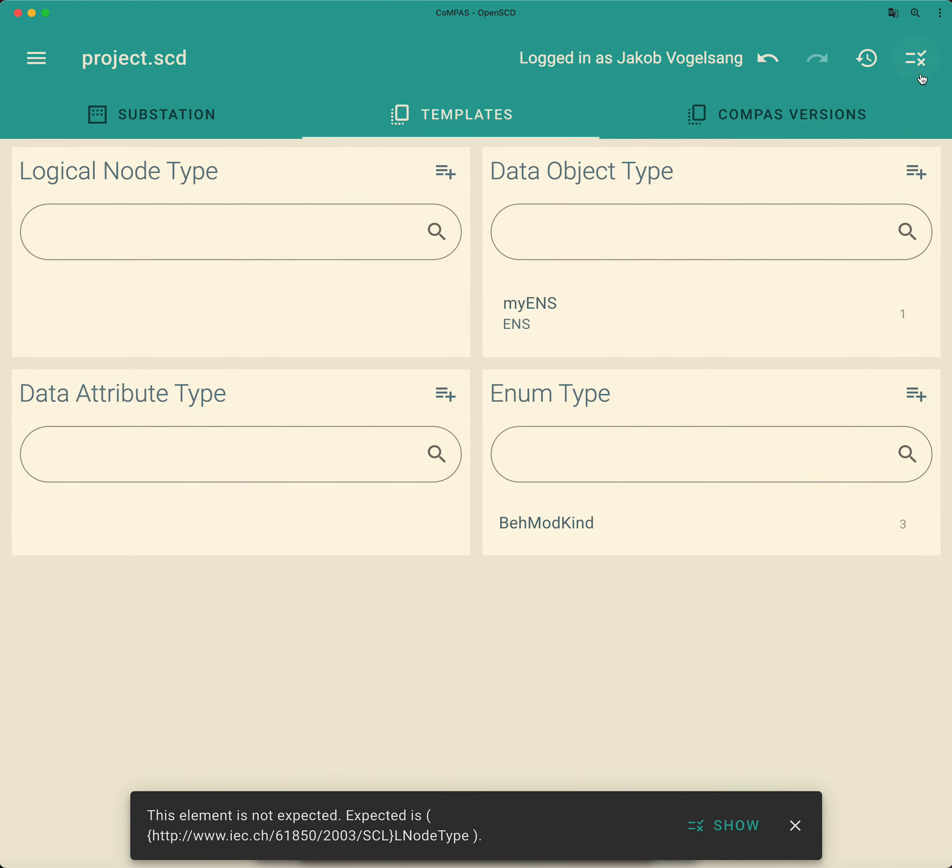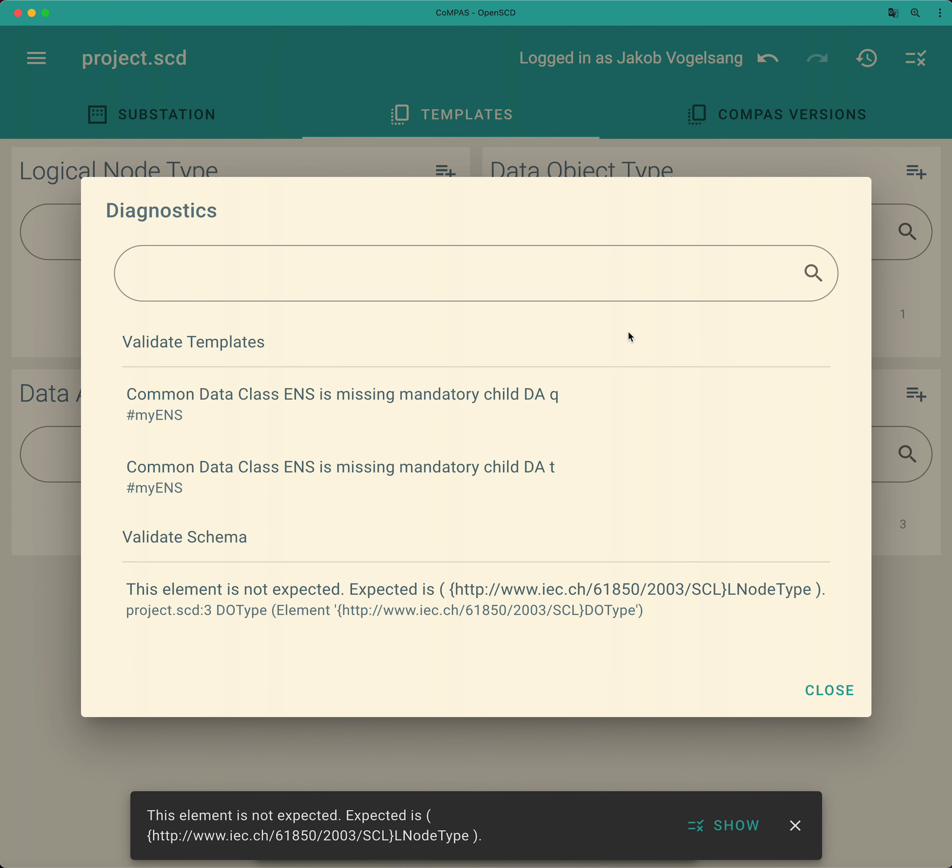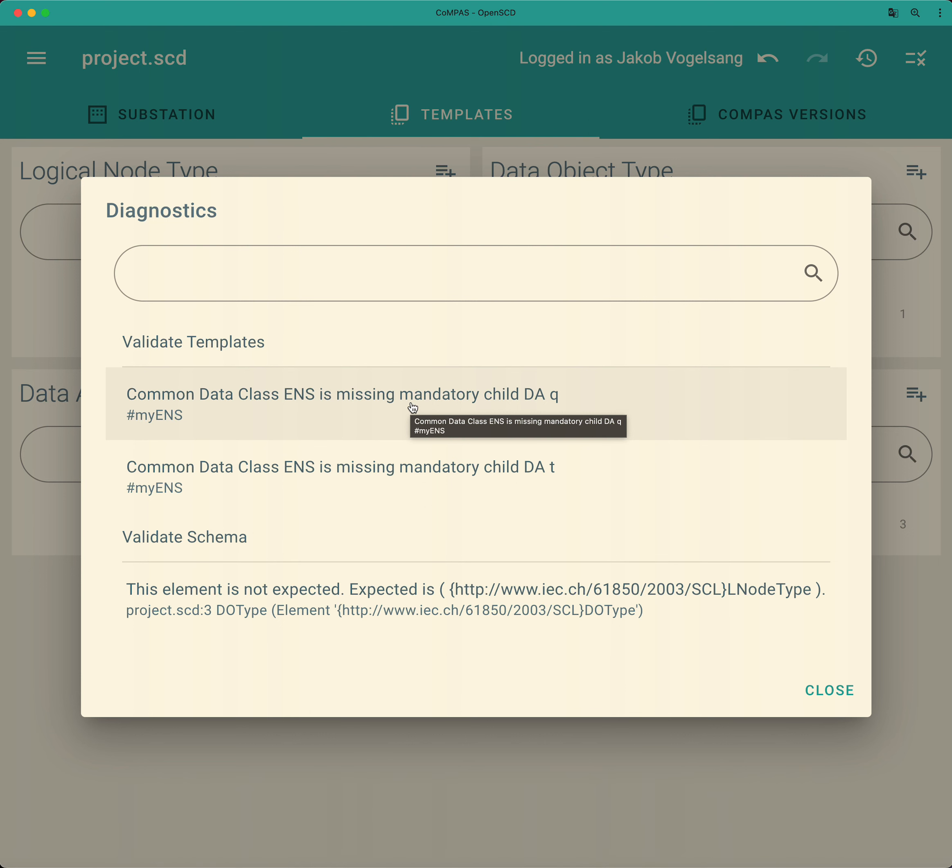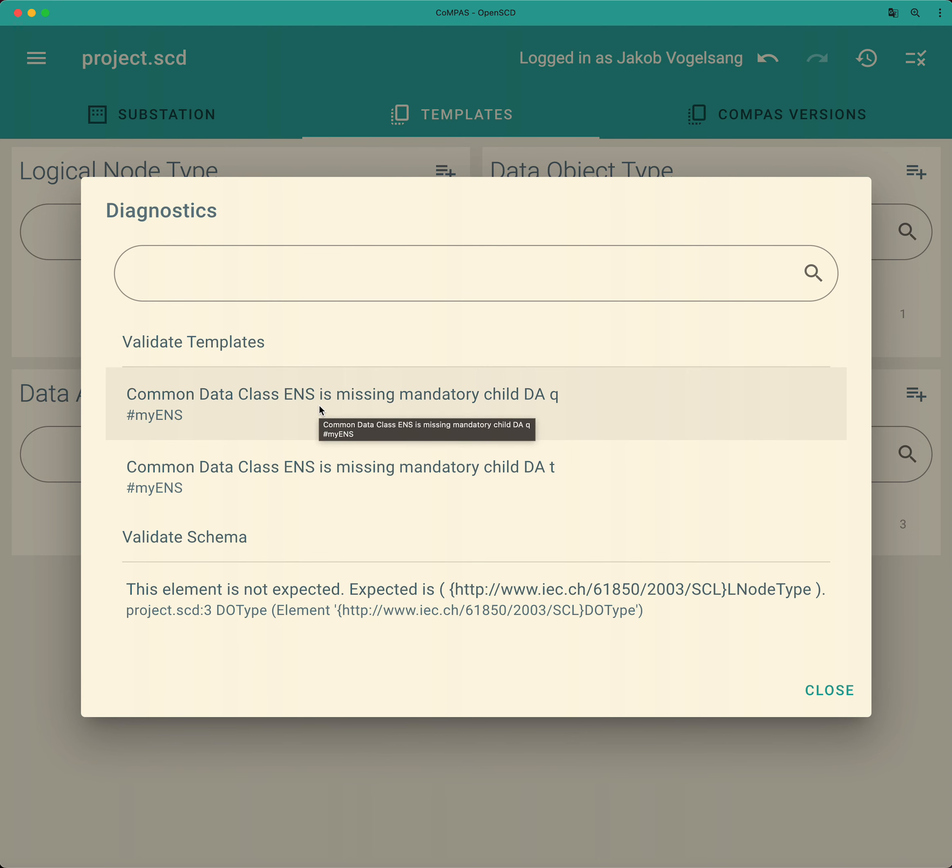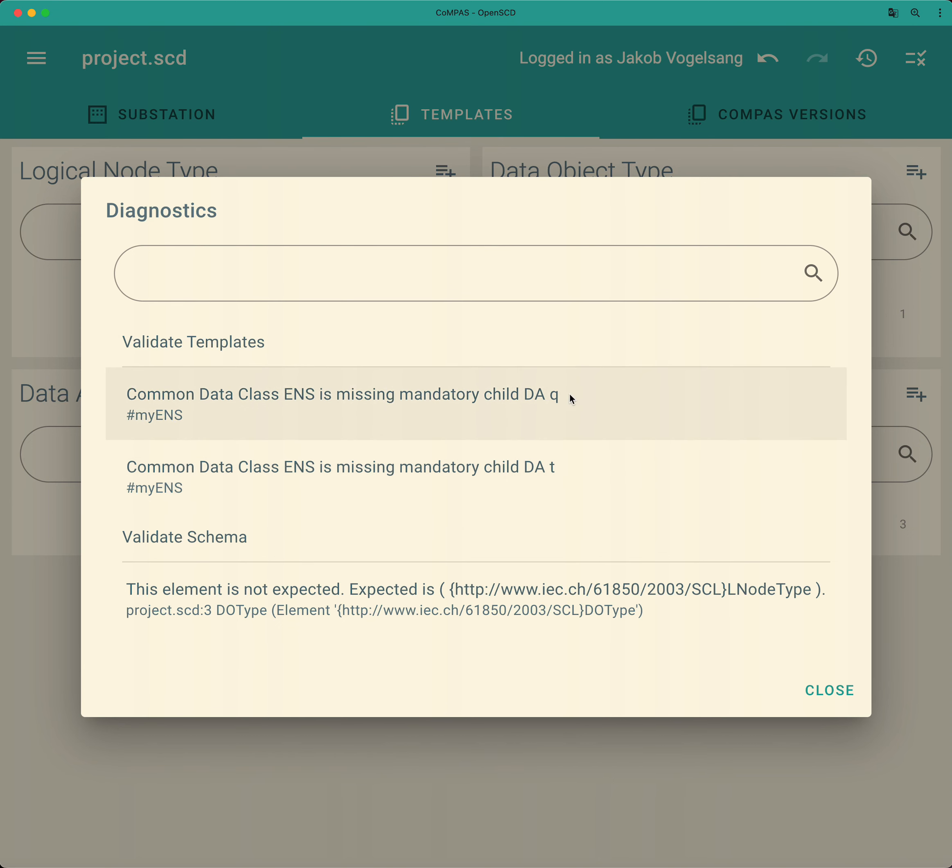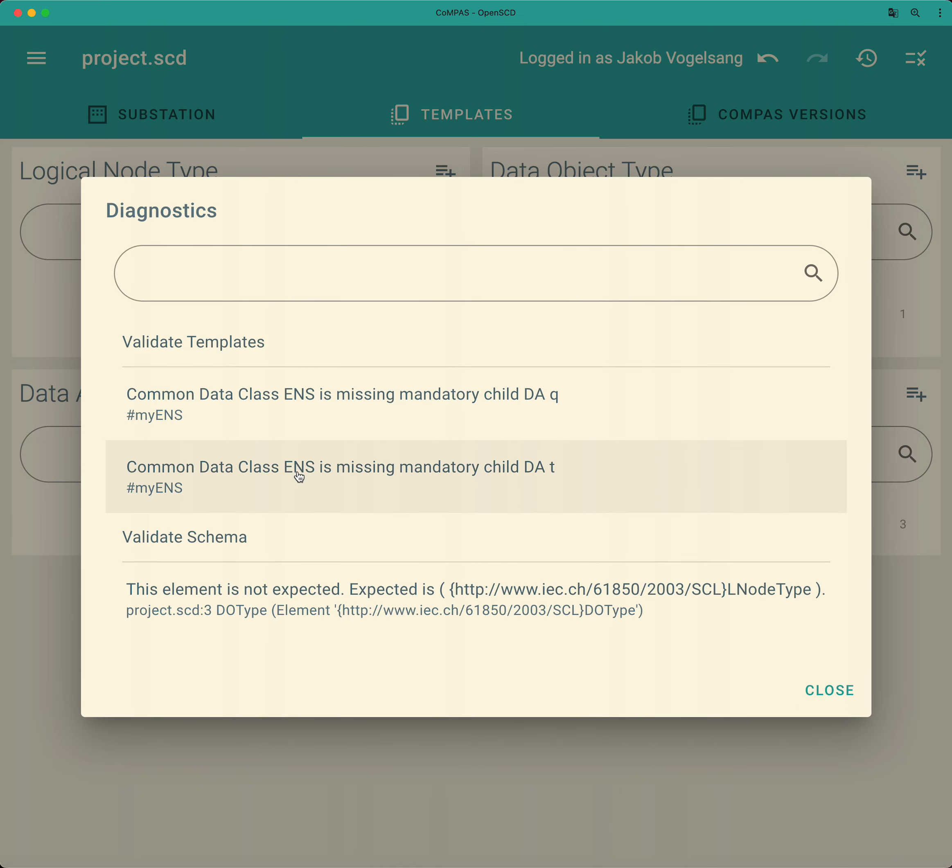Now, the template data that is running in the background has some capability to check whether the data structure that you have created does fit to the standard. And one of the things that we're checking is whether mandatory data objects, data attributes are added to the structure. Here for example, template validator tells you that the quality and the time information is missing right now in the common data class ENS.